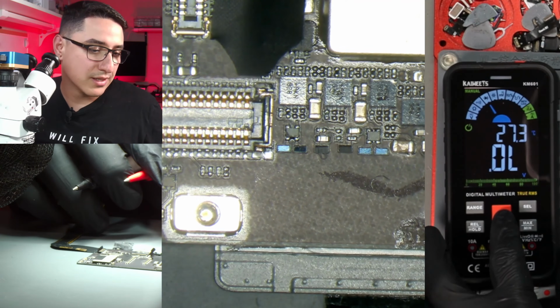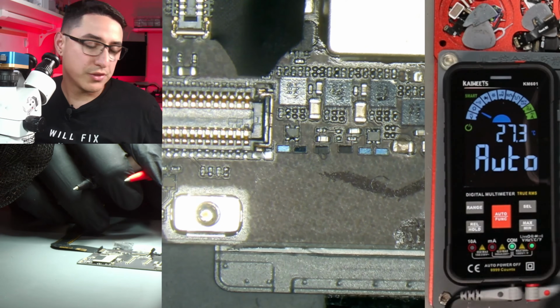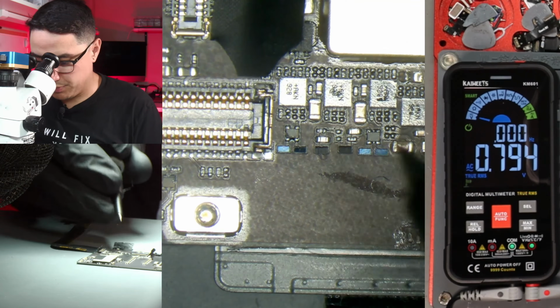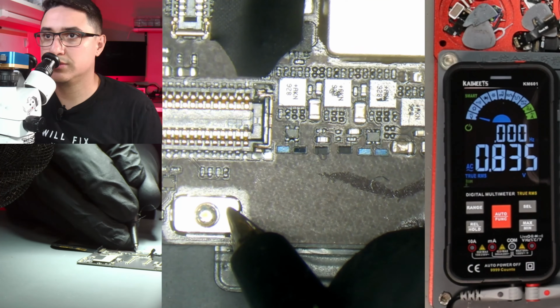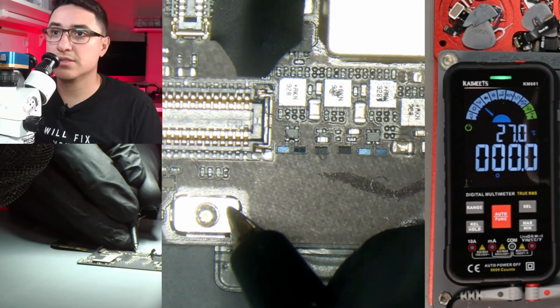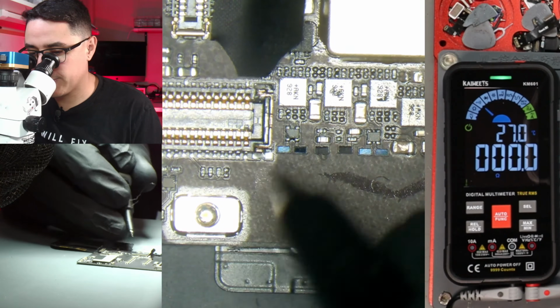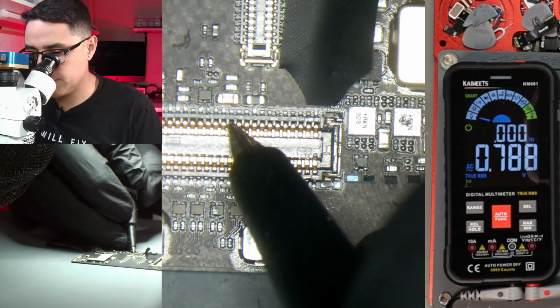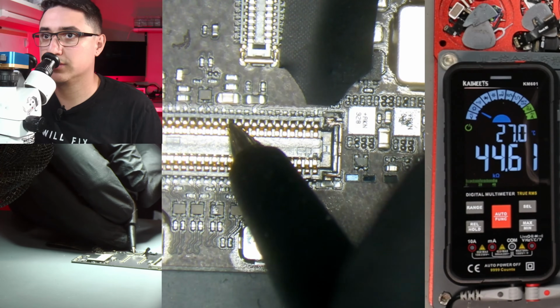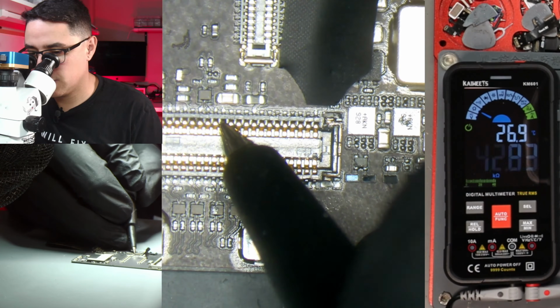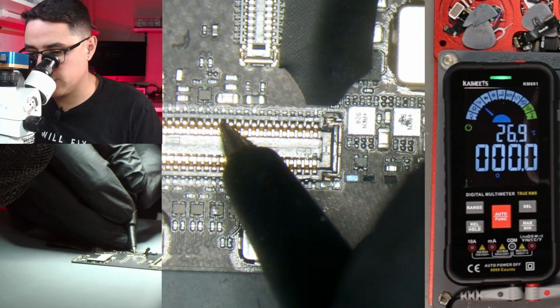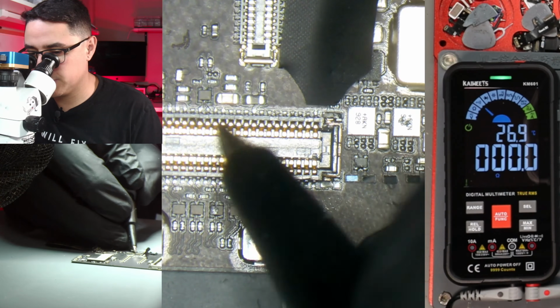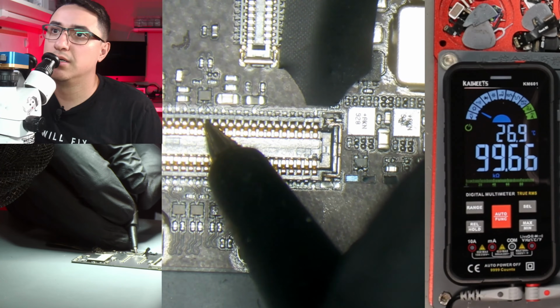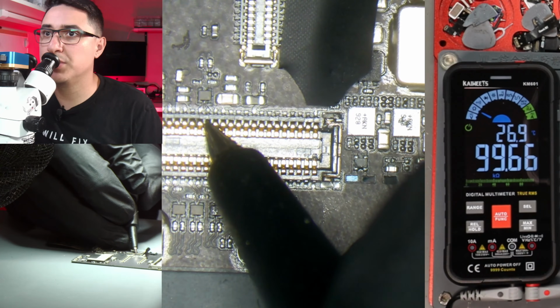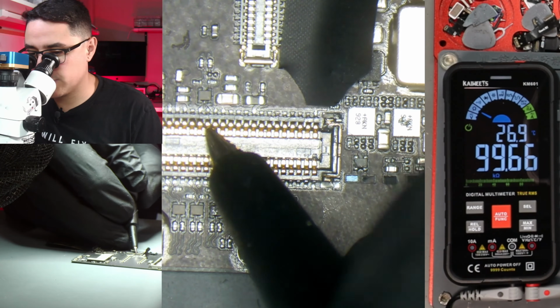If you do want to check for shorts, you would have to basically go back into continuity mode. So you put it in auto mode and then probe. There it goes. It did take a little bit. Some of these pins are ground. Yeah, see, like this one's ground and it beeps. Long beep. Yeah, so auto mode is measuring resistance right now.